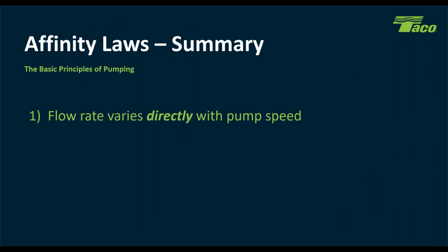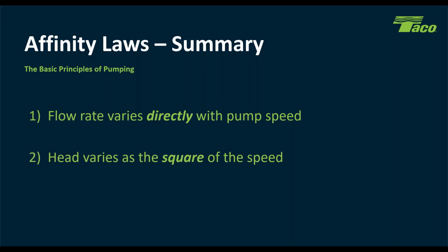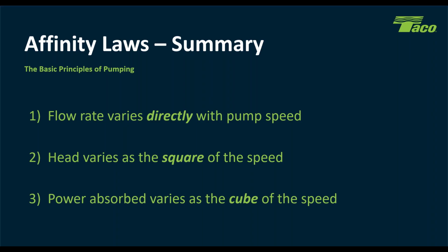So what we have to understand is all this is working on the affinity laws that we should all know. We know that through the affinity laws, flow rate varies directly with pump speed. So 100% speed is 100% flow, 50% speed is 50% flow. That's the real simple one. We also know that head varies as the square of the speed. So the head's going to move up and down as we square the speed up and down. And then this is the one that's really important to understand: power absorbed varies as the cube of the speed, or the brake horsepower varies as the cube of the speed. This is where VFDs really shine because of the energy savings that happen with putting a variable speed drive on fans and pumps.